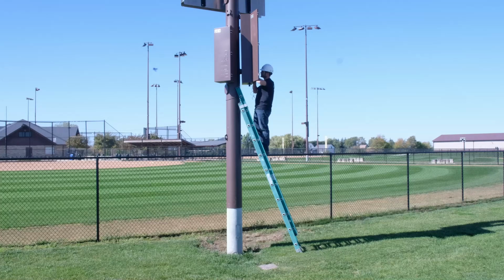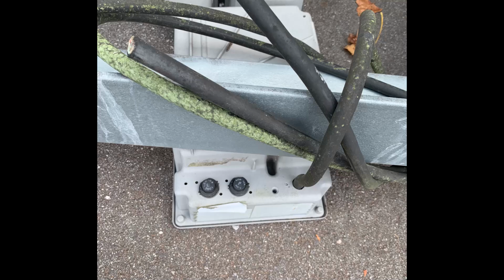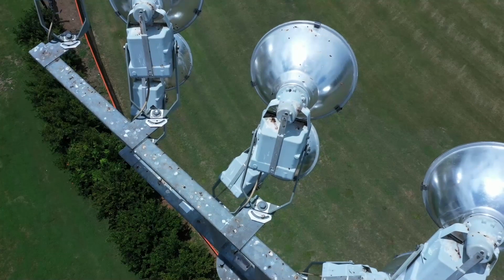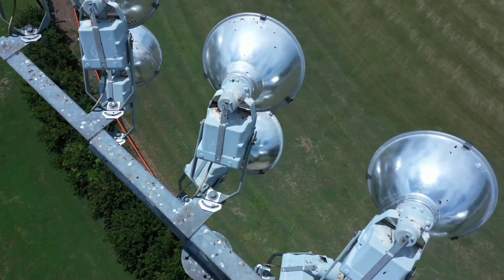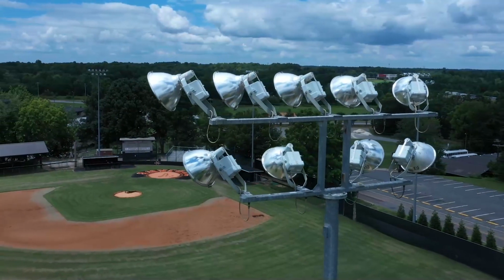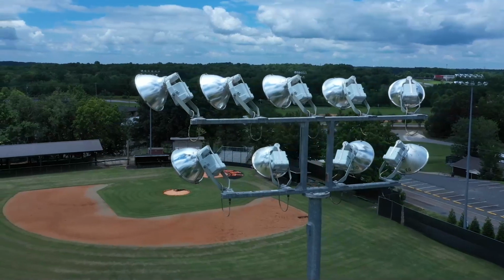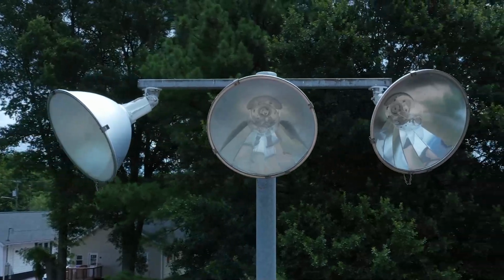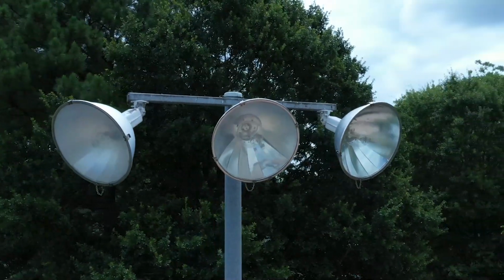ground in those cabinets. In other systems where the ballast and the driver are located integral, the fuses will be mounted and located at the top of the pole. Some manufacturers don't install fuses at all. Again, to reinforce the importance of fuses, they protect individual components of the lighting system, such as ballasts and drivers. This isolates a problem to one fixture and prevents a complete pole outage.